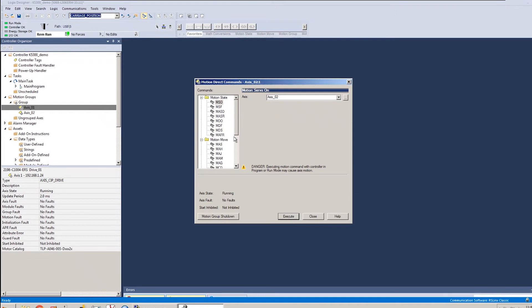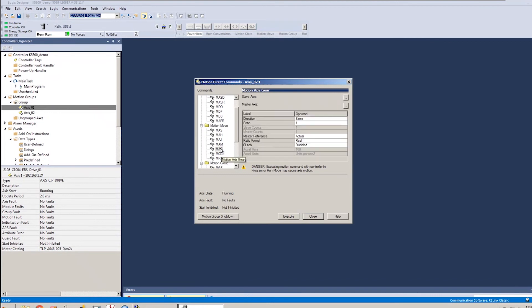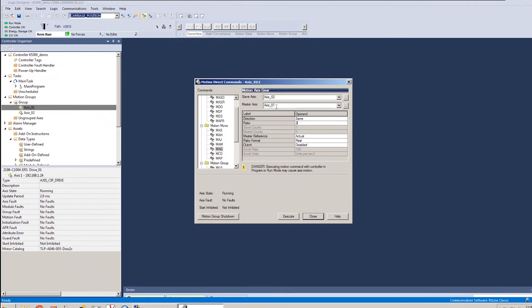Now there's a variety of motion instructions in here that I can run on these axes. For this demonstration, I'm just going to go to axis two. I'll enable a gear instruction, set my ratio to, let's just go with a ratio of two. And in this case, the master's axis one, the slave is axis two. And I'm going to execute that gear instruction. So now axis two is geared to axis one.